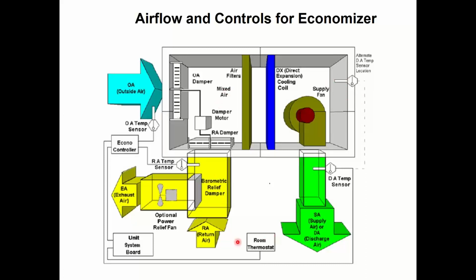So thermostat asks for cooling. Economizer says, yes, it is nice outside. Let's do this. He starts modulating the outside air damper to maintain 53 degrees right here. Then I get a degree or two of waste heat off of the motor, which means I end up with 55 in the supply duct, which is what the vast majority of cooling systems are designed to provide with their compressor anyway. If I can get you 55 degrees in the supply duct with the outside air damper, there's no reason to run your compressor. I'm good. I'm covered. Done, right?